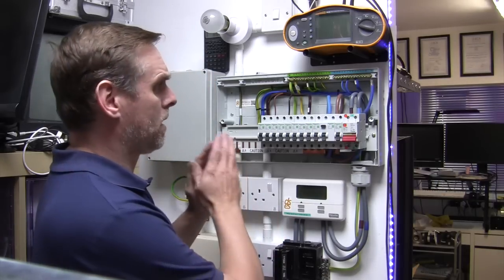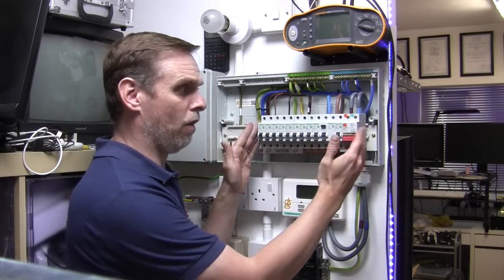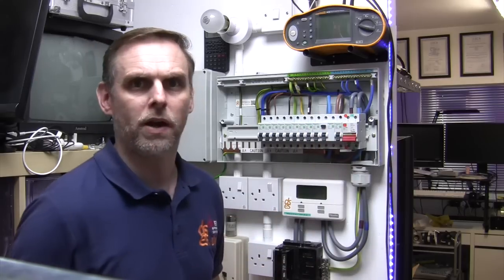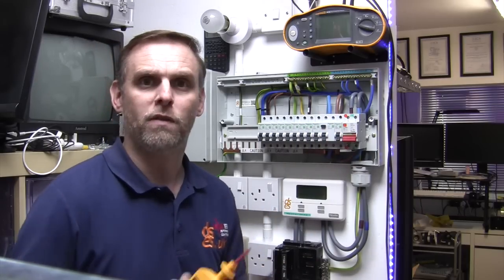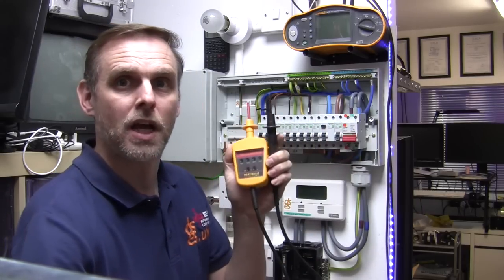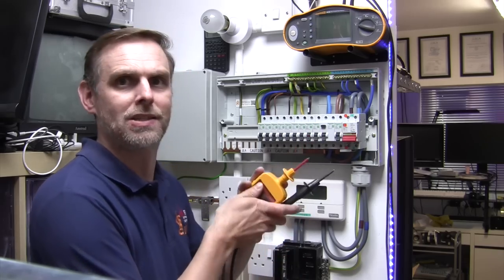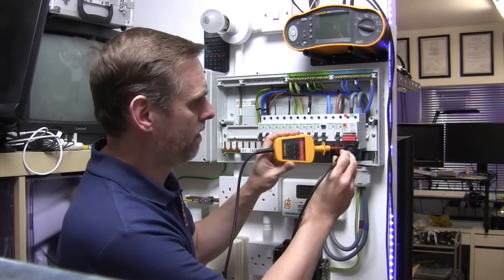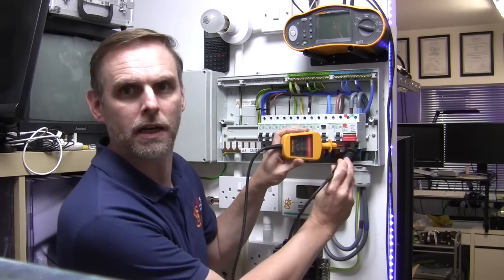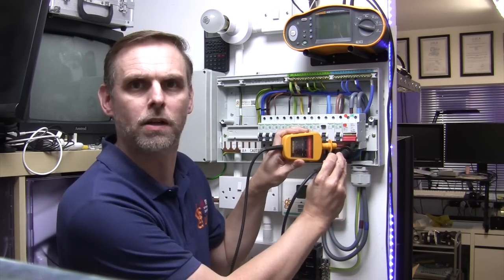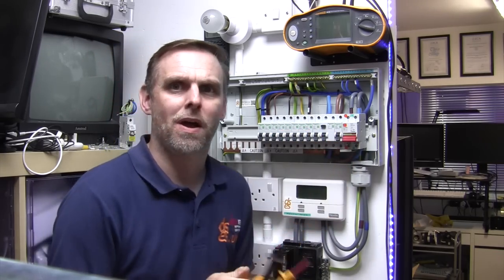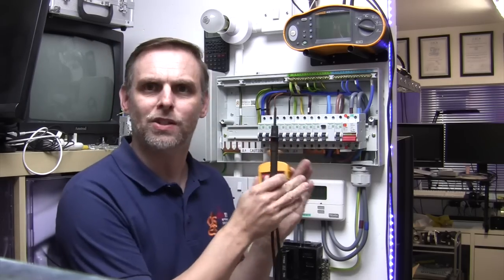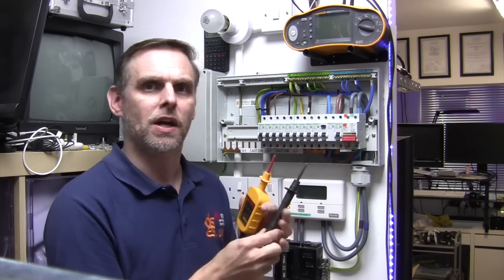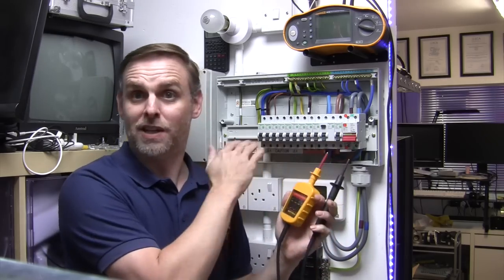Okay, so my consumer unit is off, it's isolated. Obviously we've still got power going into the main switch. Now I've already proven my voltage indicator is working, so if I use that now to test the output side of the main switch, then hopefully indeed it reads that it's dead. I'm getting no lights lighting up there. However, we've got no reading line to neutral on the output side of the switch, so the downstream circuit that I intend to work on should be safe.